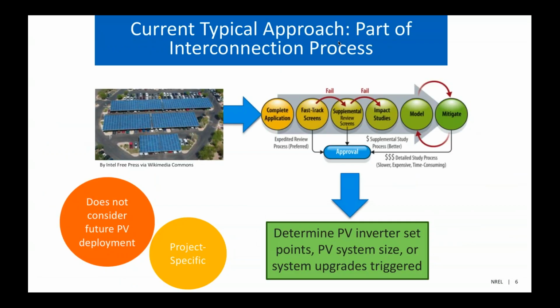So how are these issues that may need to be mitigated typically identified? A PV project usually applies for an interconnection application, and that's what this flow chart is showing here. After that, they go through a different set of screening and review processes depending on the characteristics of the system. These can include fast track screens, supplemental review screens, more detailed impact studies, and then the utility does modeling and suggests solutions for mitigating the impacts, if any are observed.